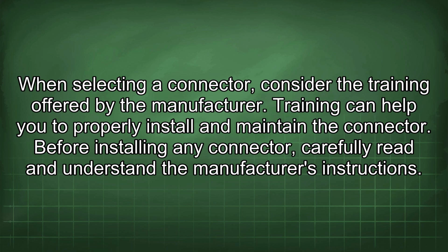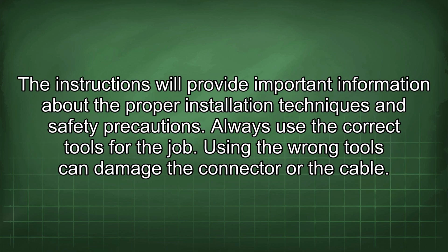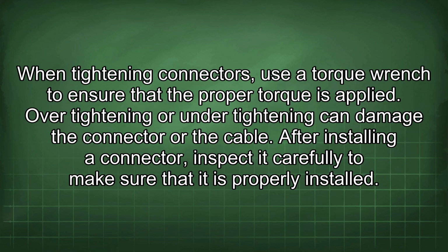Before installing any connector, carefully read and understand the manufacturer's instructions. The instructions will provide important information about the proper installation techniques and safety precautions. Always use the correct tools for the job. Using the wrong tools can damage the connector or the cable. When tightening connectors, use a torque wrench to ensure that the proper torque is applied. Over-tightening or under-tightening can damage a connector or the cable.